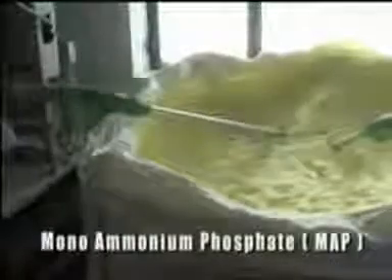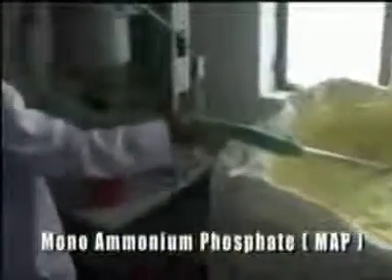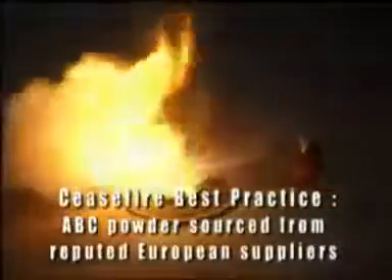Moving on to Ceasefire's extinguishing powder, the powder that puts the fire out. The active firefighting ingredient in ABC powders is a chemical called monoammonium phosphate, or MAP for short. ABC powders are available in various strengths, with MAP levels going from 10% up to 90%. Ceasefire sources its ABC powder from the most reputed European suppliers, whose products are tested in laboratories across the world. Ceasefire's technical team also retests the powder independently.